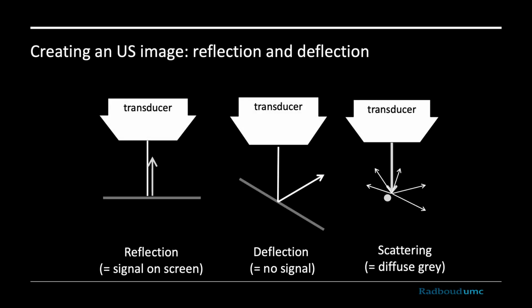Well, your ultrasound machine sends out sound waves, and they will only produce an image on the screen when they are reflected back from whatever you're looking at at an exact 90-degree angle, returning to the probe. If they are deflected, like in the middle of this slide, no sound will get back to the transducer and no image will show up on the screen. Finally, the sound wave can encounter something that's smaller than the wavelength of the emitted frequency, scattering the image. And this is the image you would get when you scan a liver or thyroid or a very dystrophic muscle. In summary, you do need to keep that 90-degree angle to whatever it is you're scanning. And if the nerve goes obliquely under the skin, you will need to adjust the probe angle to keep that exact 90-degree angle.